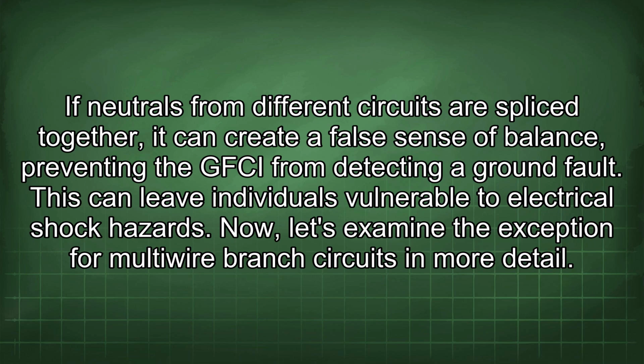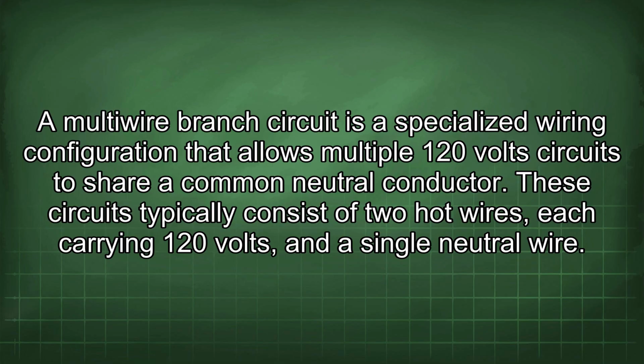Now, let's examine the exception for multiwire branch circuits in more detail. A multiwire branch circuit is a specialized wiring configuration that allows multiple 120-volt circuits to share a common neutral conductor. These circuits typically consist of two hot wires, each carrying 120 volts, and a single neutral wire.